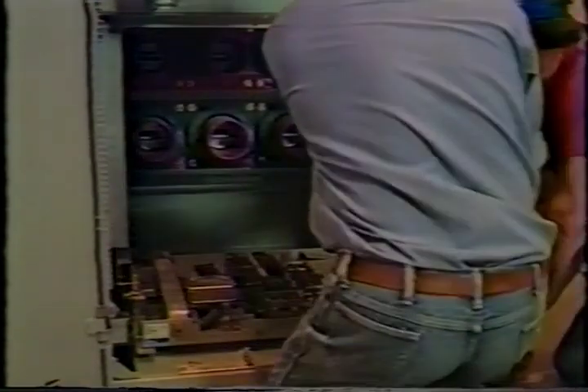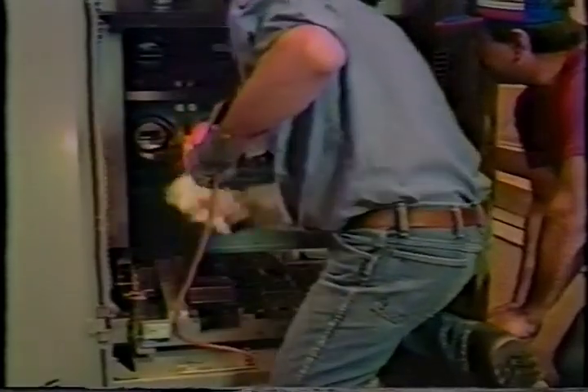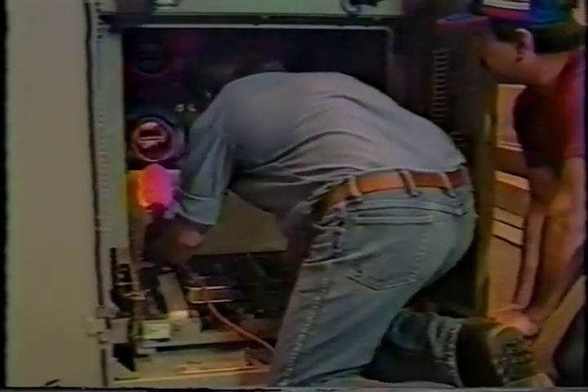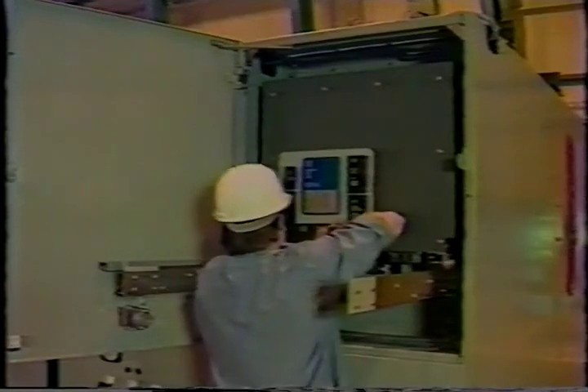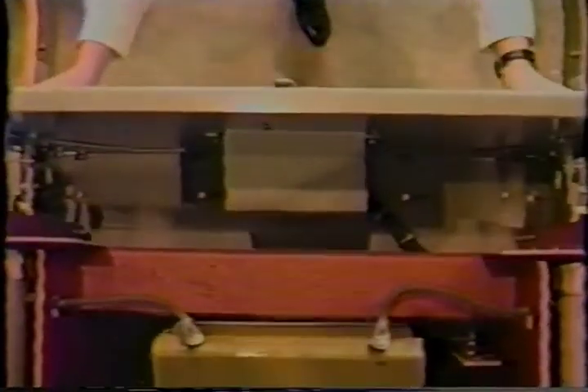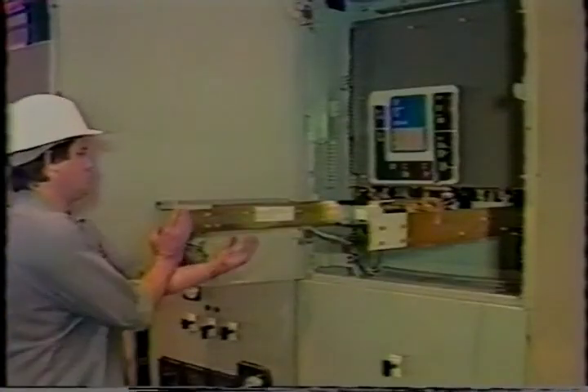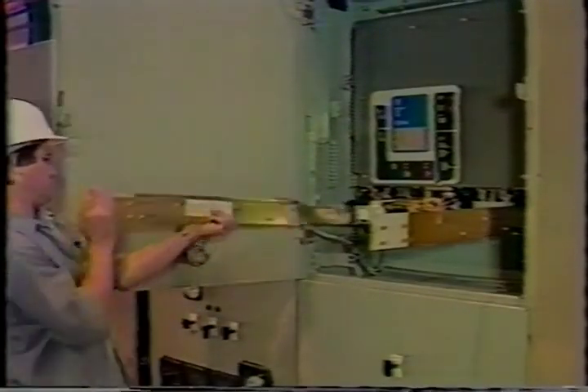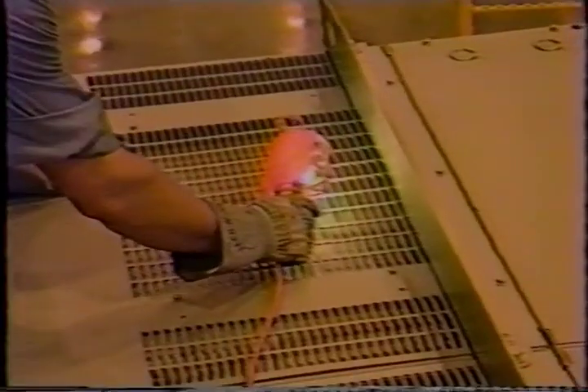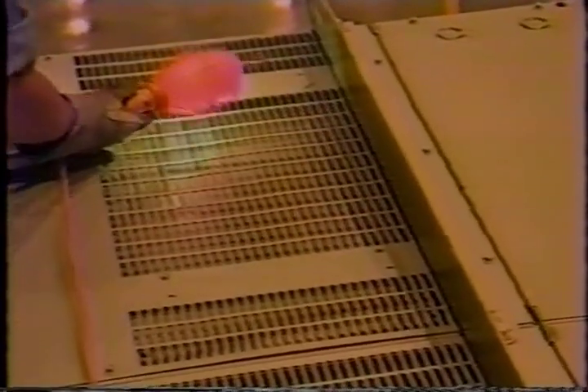Visually check and manually operate mechanical moving parts such as the shutter, the position interlock, hinged doors, and the draw-out features of the transformers and fuses. Examine mechanical mating parts such as the breaker secondary contact blocks, side rails, and trippers. Check all labyrinths, grill work, and air passages for obstructions and accumulations of dirt.